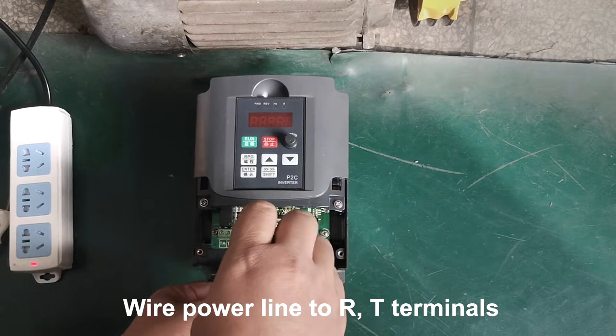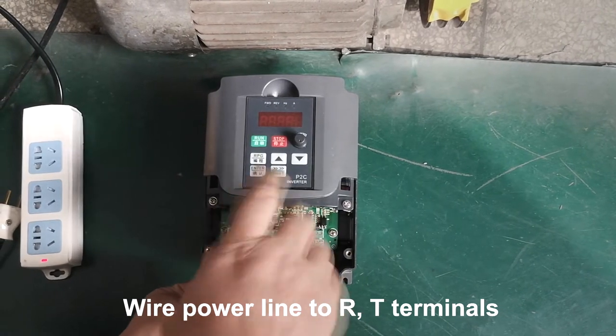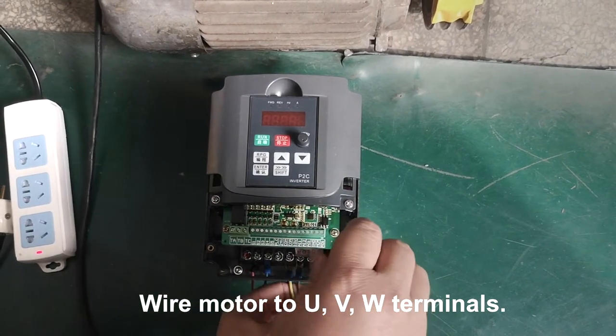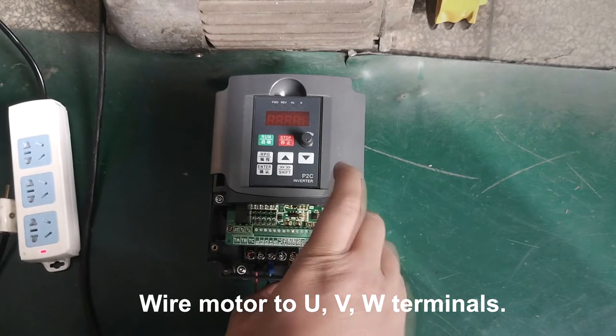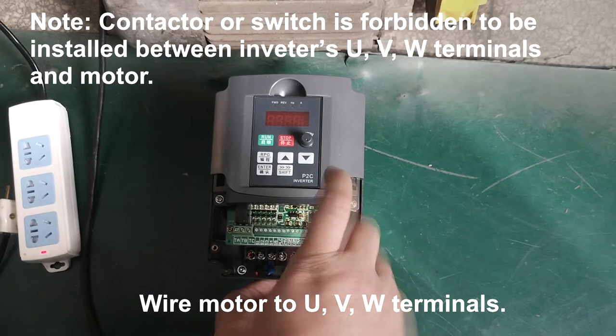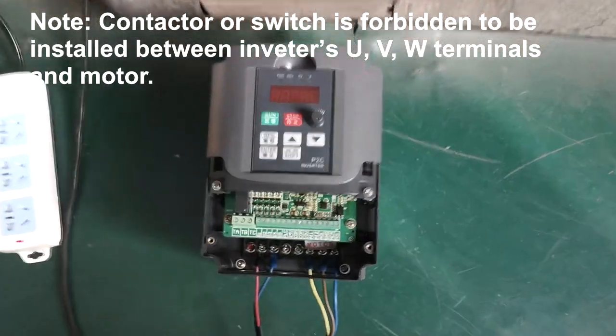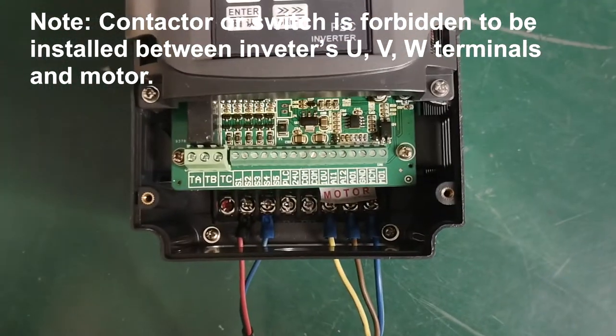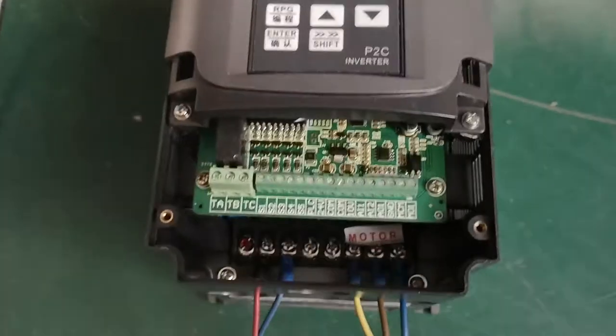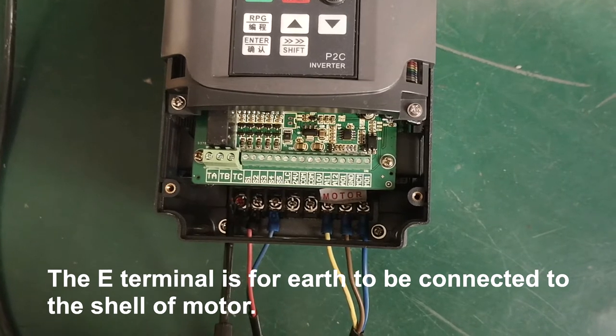Wire the power line to R, T terminals, then wire the motor to U, V, W terminals. Contactor or switch is forbidden to be installed between the inverter's U, V, W terminals and the motor. The E terminal is for earth to be connected to the shell of the motor.